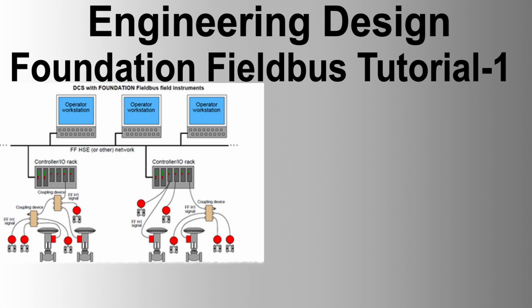Link maintenance. The third role of LAS is to maintain the link. The LAS gives the token to all devices detected by the LAS. When a new device is added to the network, it must be recognized by the LAS and entered into the token rotation list called live list. The LAS sends a probe node, PN, PDU to node addresses where a device was not found before. When a device is removed from the link, it does not respond to PT anymore. The LAS detects this and deletes the device from the live list.